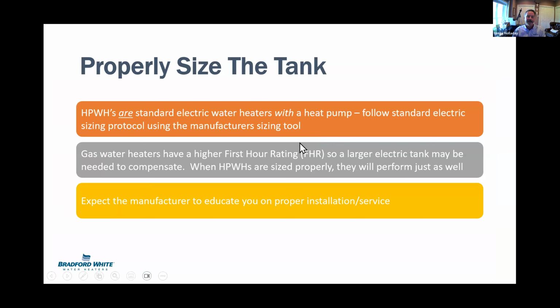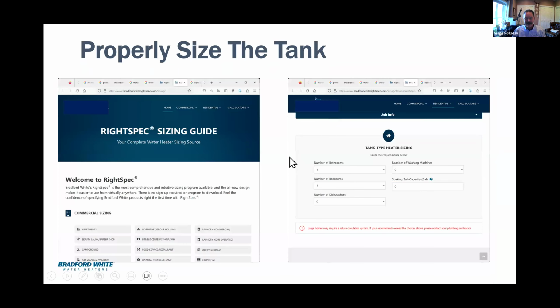Properly sizing is probably one of the most important things we teach contractors, especially if they're operating in a market that's doing fuel switching from gas to electric. In that case, 50-gallon electric, 50-gallon heat pump water heater, or electric water heater of any kind is not equivalent, because gas water heaters have a 40,000 BTU blowtorch. Electric water heaters have a 4,500 watt heating element, and that's it. So always remember that it should be sized according to what the manufacturer says.